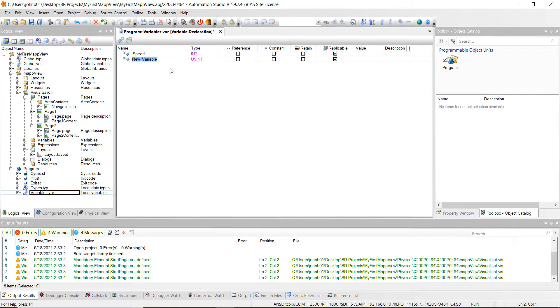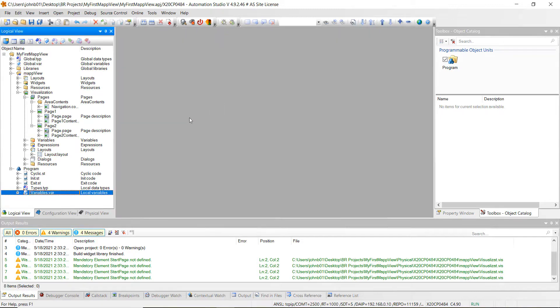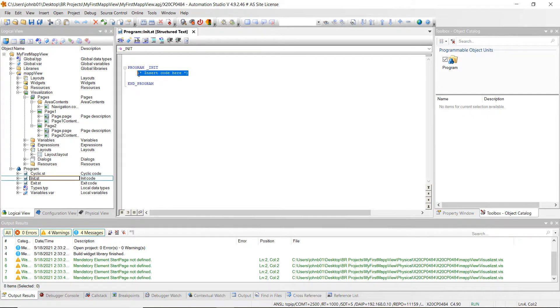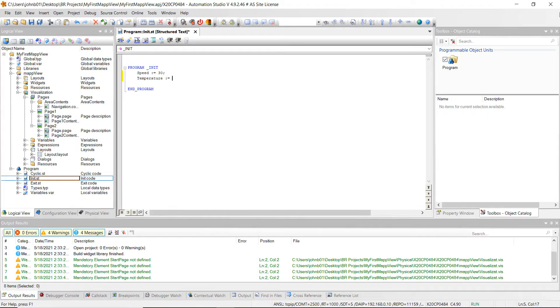Let's go ahead and add another variable and we're going to make this temperature. We're going to have this be a real. Go ahead and click save all and then close out of there. Let's go into our initialization part of this program and insert a basic program - we're just going to set those variables. Start with speed: type SP, hold the control button and hit space bar, and it automatically populates. We're going to set that equal to 30 with a colon equals sign and semicolon. Then do temperature the same way, set it to 20 and add a semicolon. That's all we need for this program, so go ahead and hit save all and close out of there.